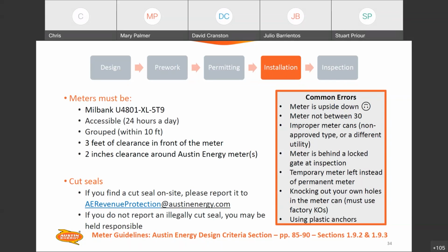Needs to be accessible 24 hours a day. Of course, if it's behind a fence and we're doing an inspection, just make sure that the homeowners are aware that inspection is happening and that we can get access to that in order to do a complete inspection. The meters should be grouped within 10 feet of each other. If not, again, you'll need to talk to Abdur and get that meter variance so that you can have an approval to place a meter can on a different wall or behind an obstruction away from the existing billing meter.